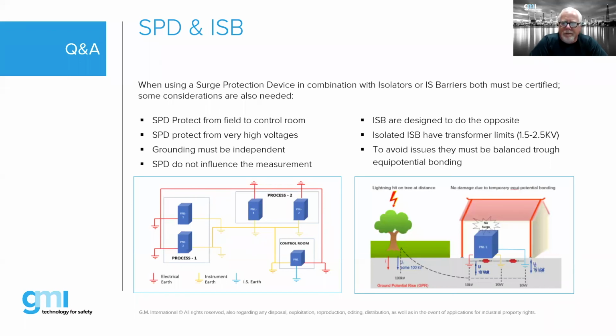So you can look at SPDs in a couple of different ways. They typically have MOVs on the inside of TVSSs, and they absorb the energy and also shunt the energy, very similar to ISBs, especially the Zener diode type, not the galvanically isolated type. So they are designed to absorb the lightning strike and then dissipate that energy to ground in a very rapid fashion. For what matters to our webinar here, what is important to understand is both need to be certified. So your SPD or TVS that you are installing into a hazardous location, or interfacing with a hazardous location, next to a barrier, must also be certified for the same use.